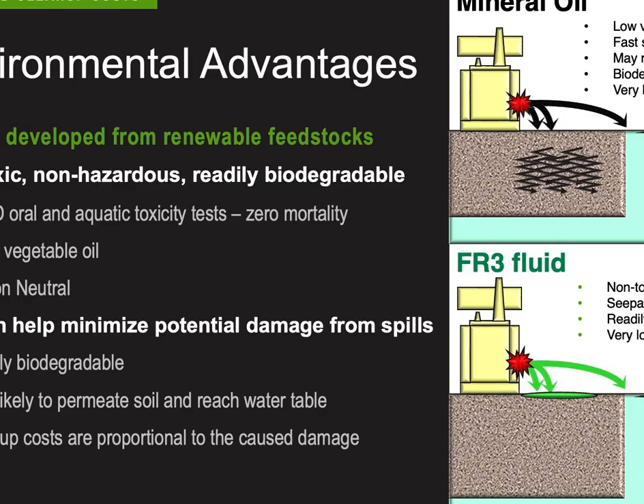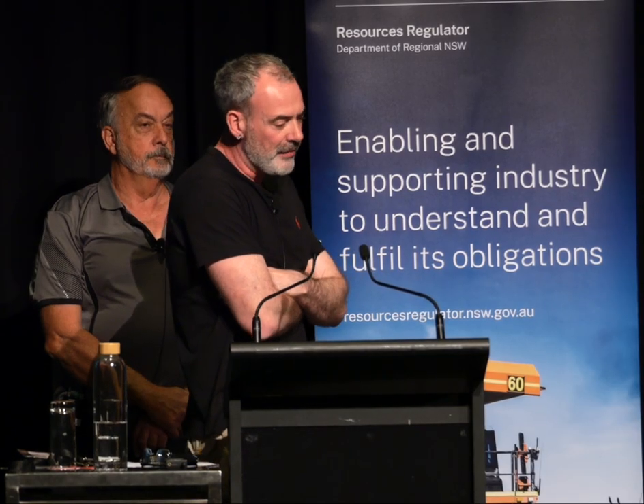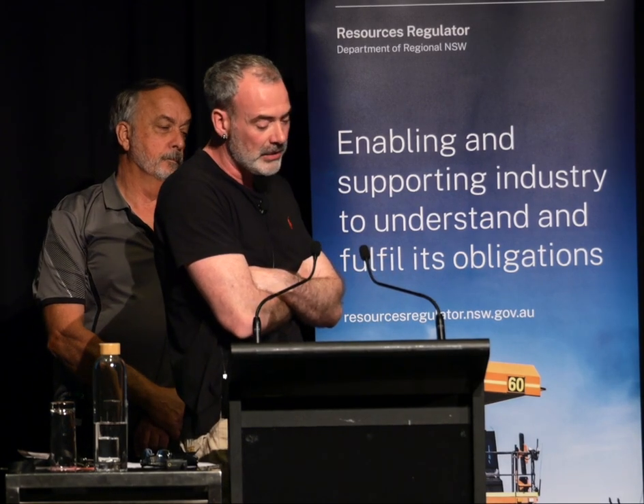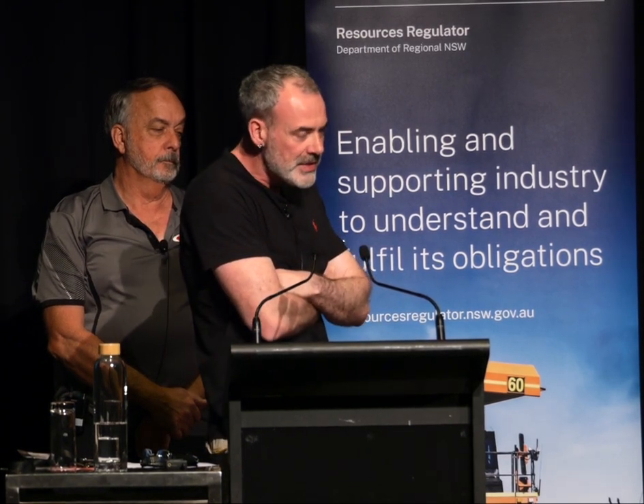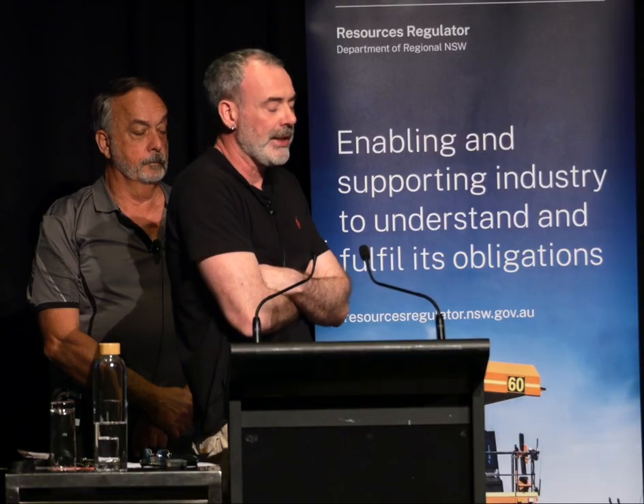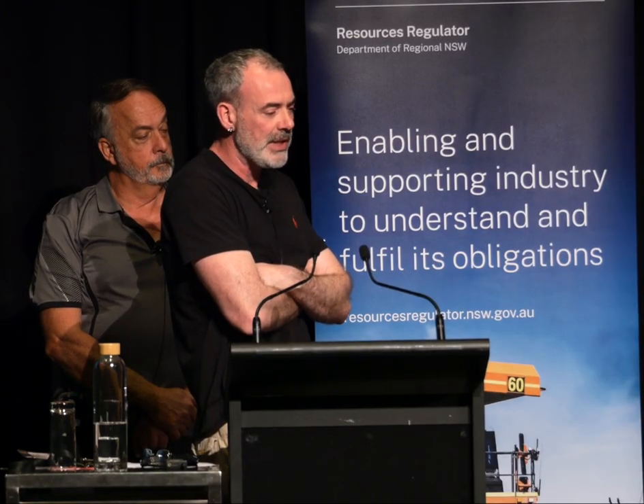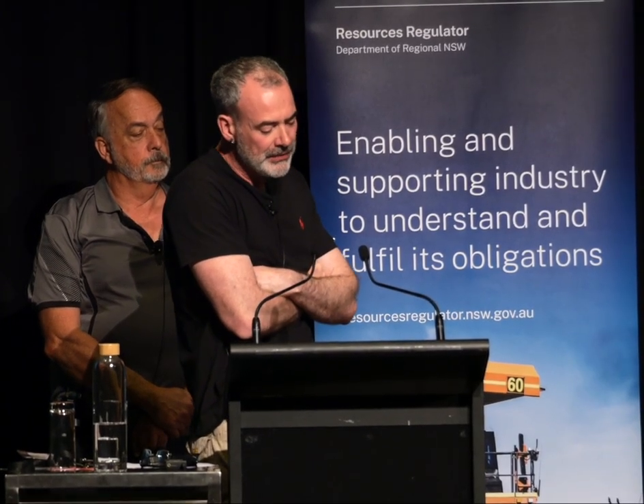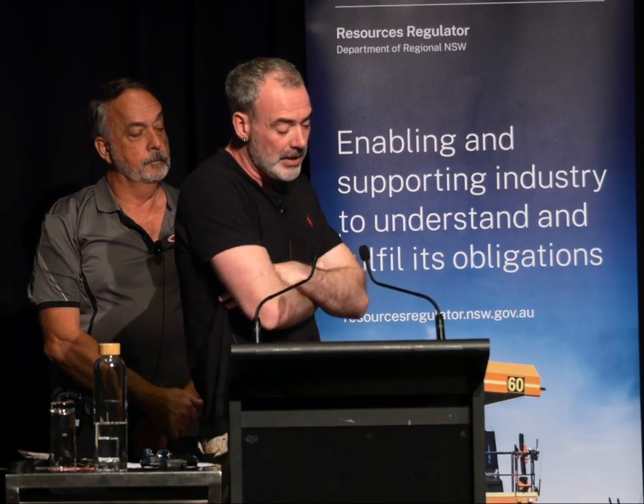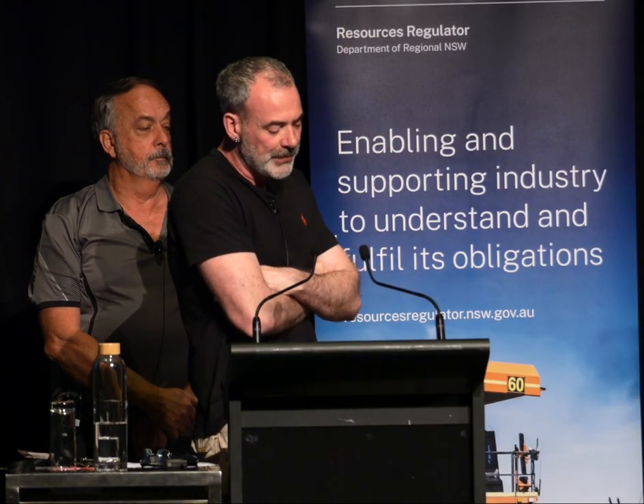So I'll move on just to some environmental considerations. If you have natural ester in a transformer, if a spill occurs, the cleanup should be easier and less expensive. FR3, for instance, is 95% vegetable oil, and the remainder of the ingredients are food grade, so that's what you're cleaning up. The higher viscosity of all ester fluids means that seepage into the soil and the water table will be more slow. And what we've demonstrated with OECD test 301 is that our natural ester is readily biodegradable. Natural ester is more biodegradable than synthetic ester and also mineral oil.